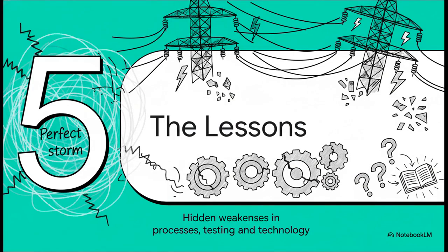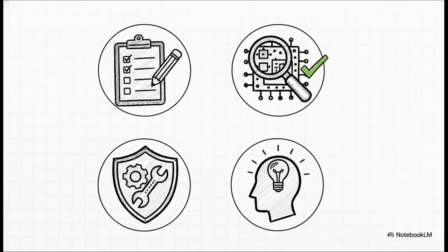So wow, this incident was a true perfect storm, a combination of events that exposed hidden weaknesses in processes, in testing, and in technology. So what are the big takeaways? The DNV report lays out several crucial recommendations. First, procedures for new equipment have to be tightened up to stop those construction phase habits from carrying over. Quality assurance and testing have to be way more rigorous to find hidden errors, like that bad wiring. Protection settings need to be audited to make sure they're compliant. And finally, employee training has to be improved. Really, it calls for a systemic focus on all those points where human processes and automated technology meet.